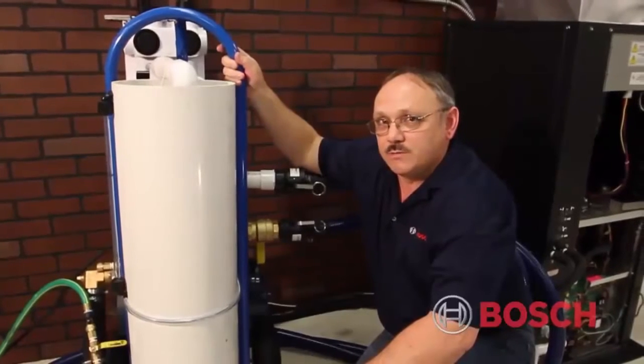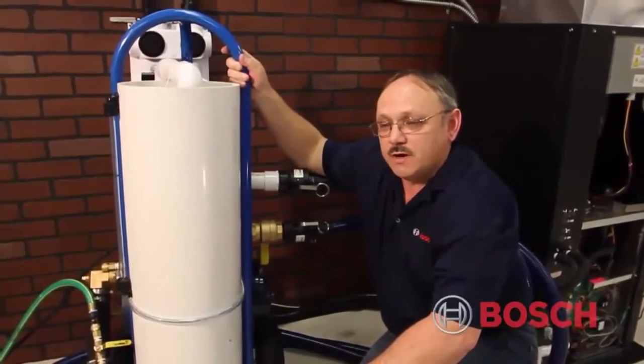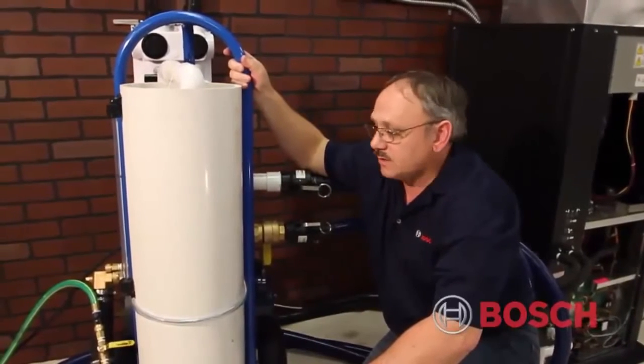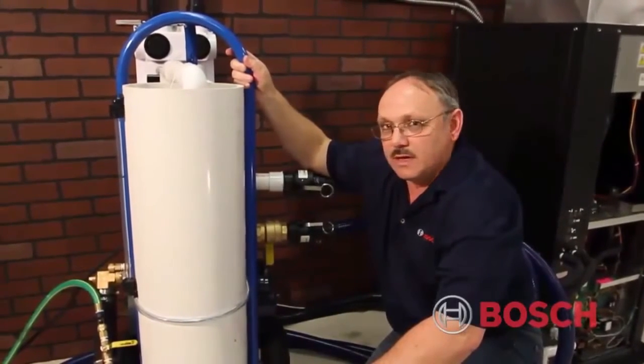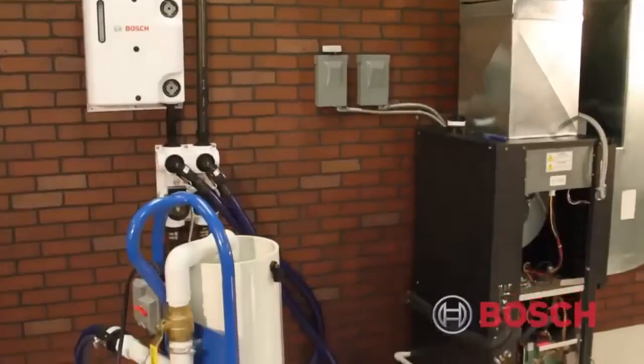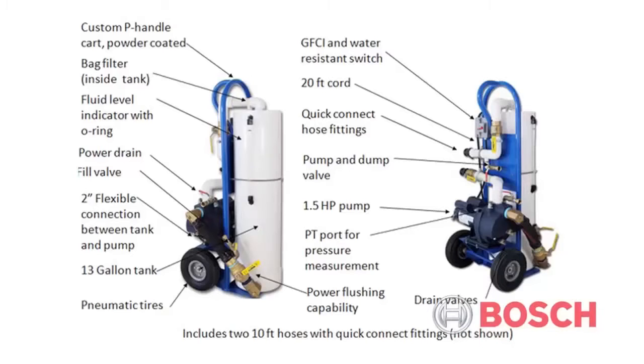The next part of our installation process is the flushing and purging of our heat exchanger and also the system side of our water piping. This is the new GeoFlow flush cart. It is available now through the Bosch accessory catalog. It incorporates a 1.5 horsepower pump, a built-in on-off switch with a ground fault interrupter on it, a 20-foot cord.